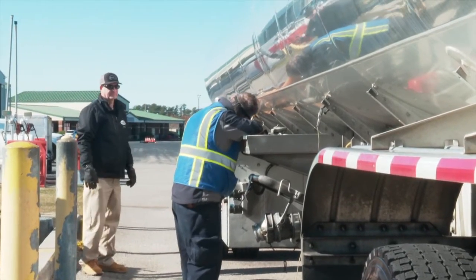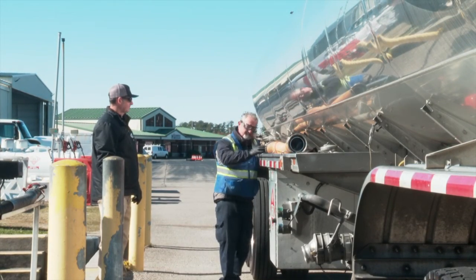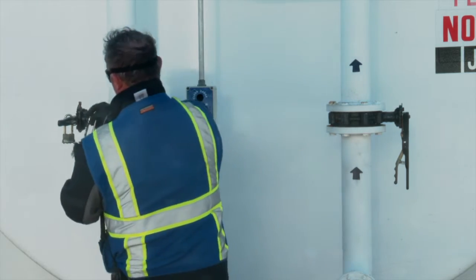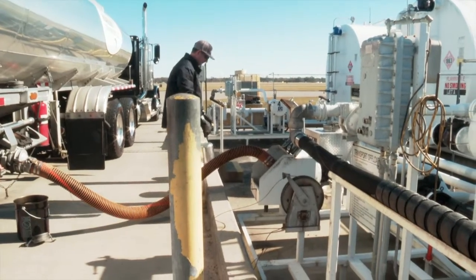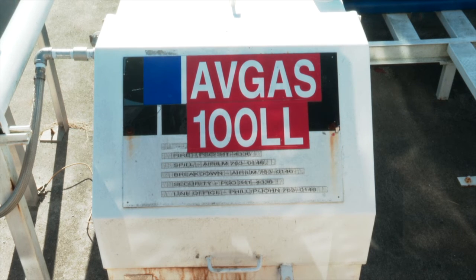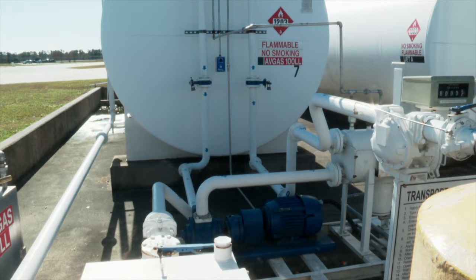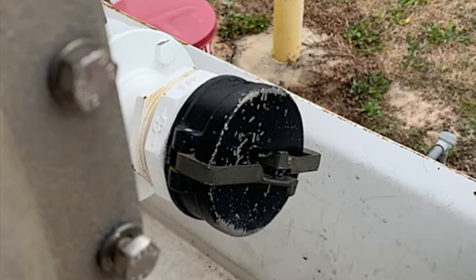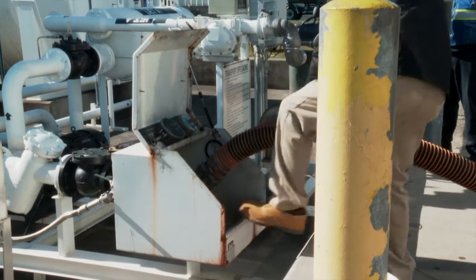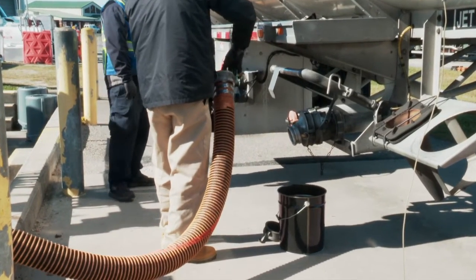The driver and the airport representative must confirm that the product is to be offloaded into the proper tank and that the offloading hose is clean and dry. All deliveries must be attended by both an airport representative and the transport driver throughout the entire delivery. Offloading shall cease if the airport operator leaves the offloading area. Aviation fuel storage is clearly marked with product-specific EI decals and product grade signs. Offload couplings for Avgas 100LL are painted red and Jet A couplings are painted black, and are grade-selective: 4-inch for Jet A and 3-inch for Avgas 100LL. Truck pumps may only be used if the pump is attached to the trailer or the truck and trailer are dedicated for one product, as truck pumps may contain dirt, water, or other products which may contaminate aviation fuels.